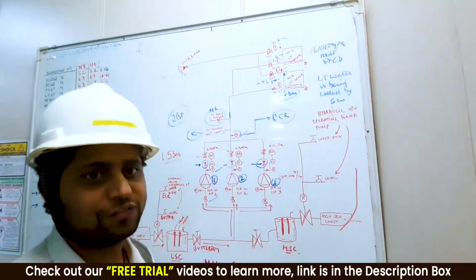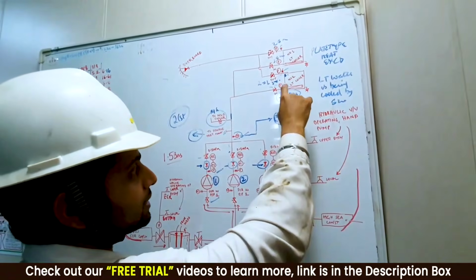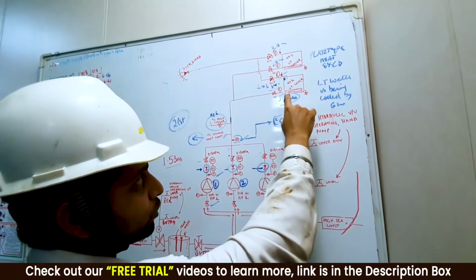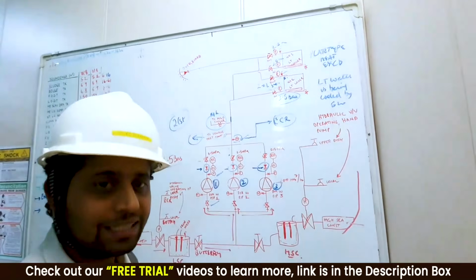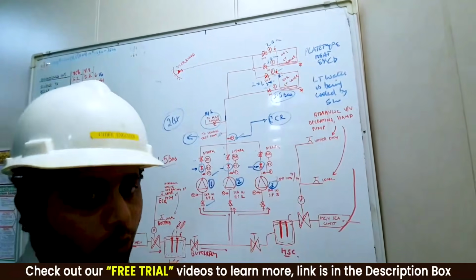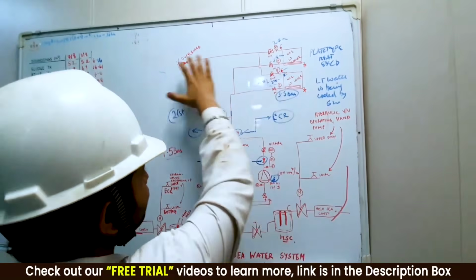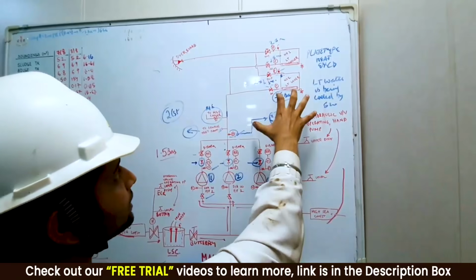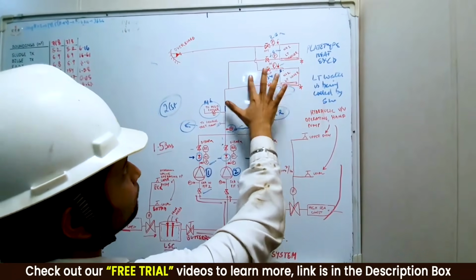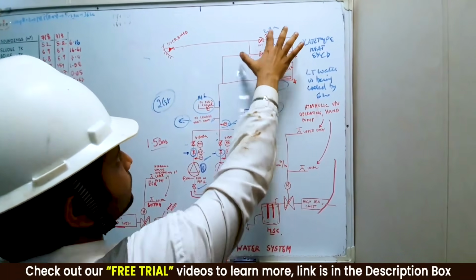So it depends where the filter is fitted, guys. The importance is where the pressure gauge is fitted, before the filter or after the filter. That decides the condition of the filter. Always very important for you to remember, guys. Copy it, guys? And then it goes overboard. So this is, guys, how you need to understand in a simple way how a main seawater system works.